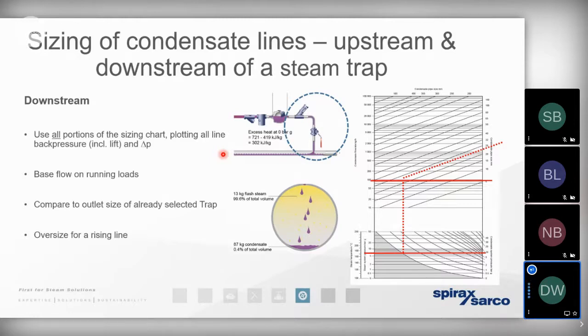Or it may travel all the way back to the boiler house and cause the feed water to have an over temperature. So we always size the pipework downstream of the steam trap, allowing for that pressure drop, which is going to result in that phase change. So please always consider condensate as a biphase, unless we know for certain it exists at a stable pressure.